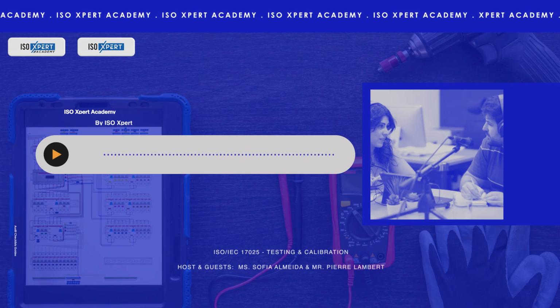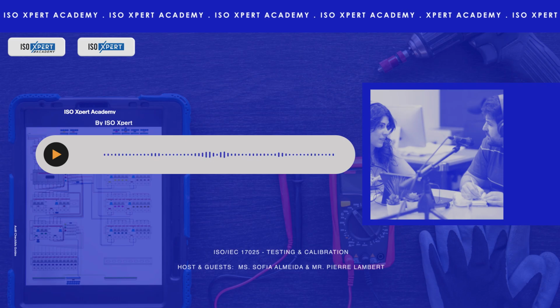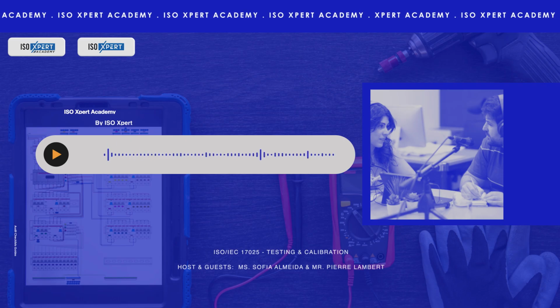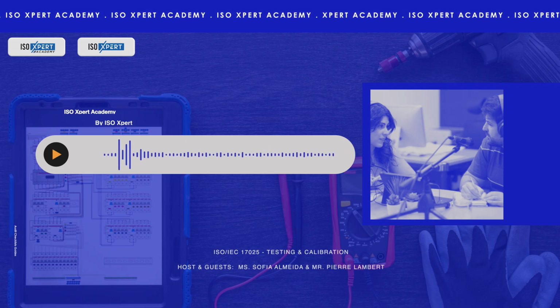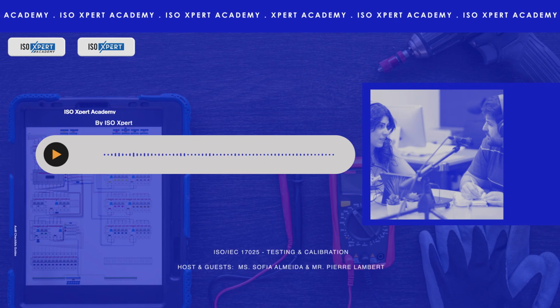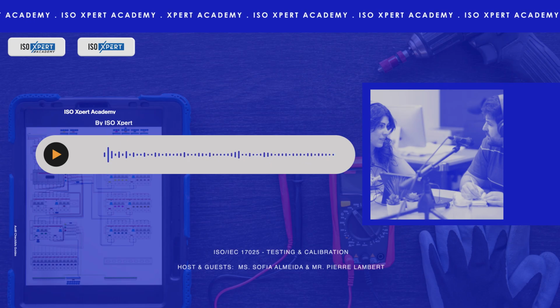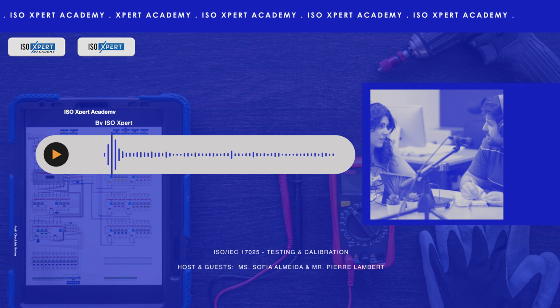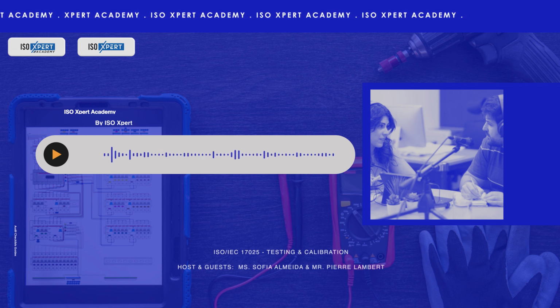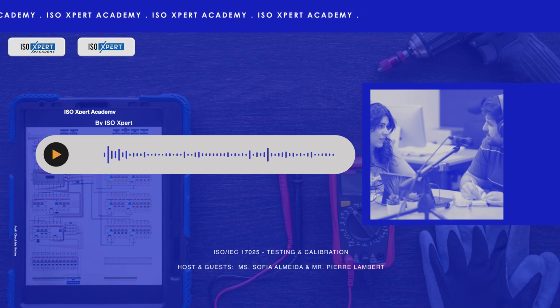This means all the controlled procedures, the SOPs we mentioned, policies, manuals need to be managed. Managed how? Making sure only the latest approved version is in use, that's version control. Having master lists so you know what the current documents are. Ensuring documents are available where needed. And for records? Like test results. Clause 8.4 covers that. Records need to be protected, stored securely, easily retrievable. There needs to be a clear record retention policy, how long do you keep things, and robust backup systems, especially for digital records.